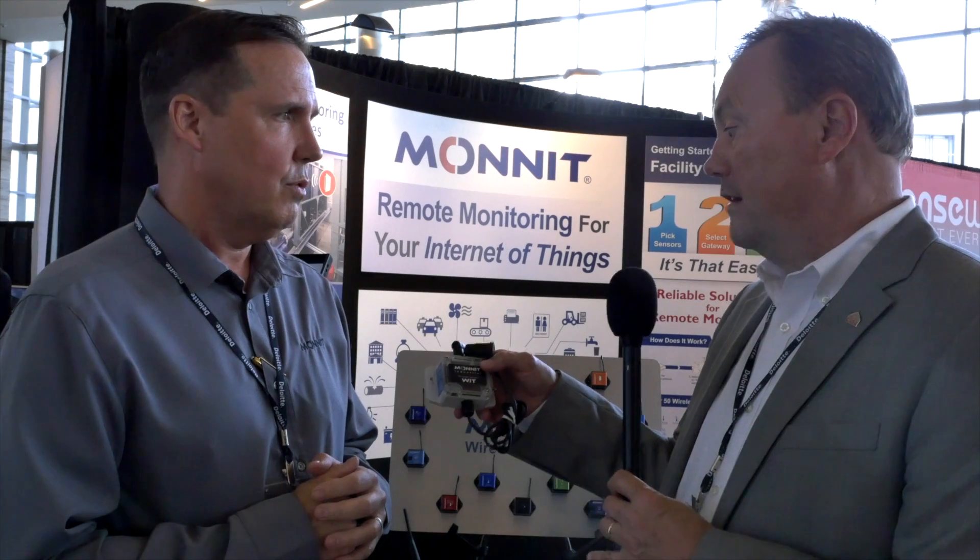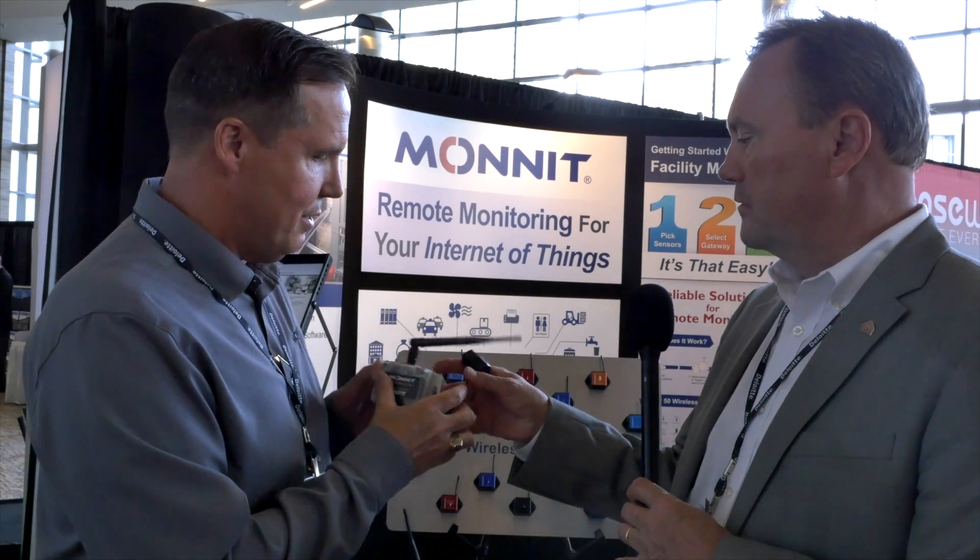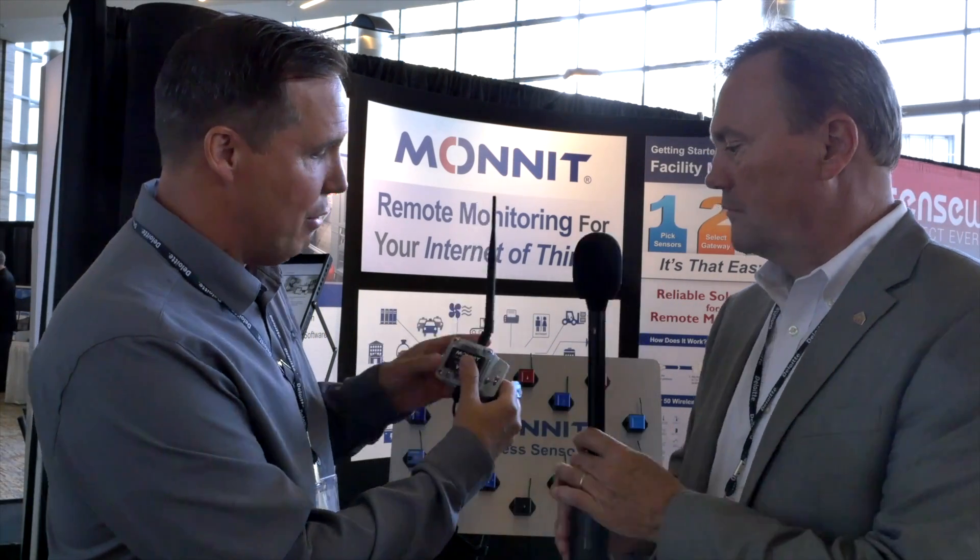For instance, I have a current sensing wireless sensor. This is a transceiver made for outdoor use, with a very low temperature tolerant battery that can go to negative 40 degrees. The battery in there will last five to seven years in very harsh environments. And this is a 20 amp current transducer — we also have 150 and 300 amp.